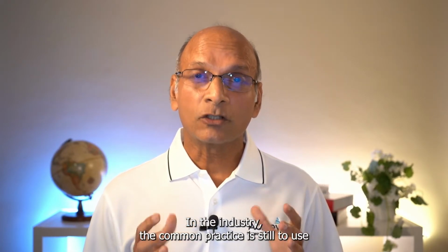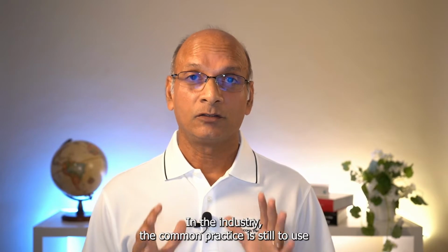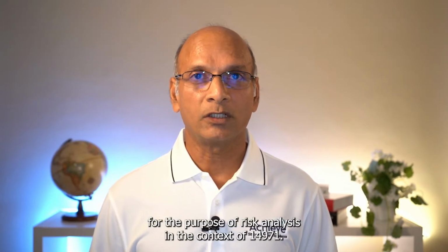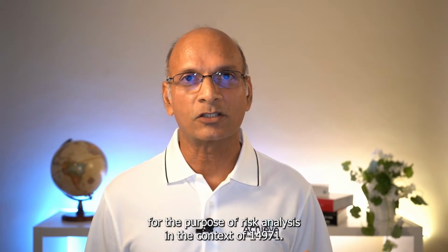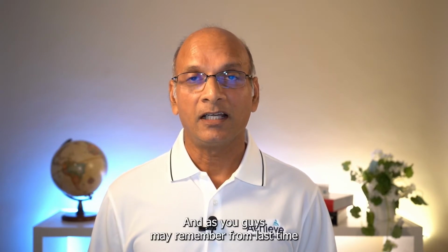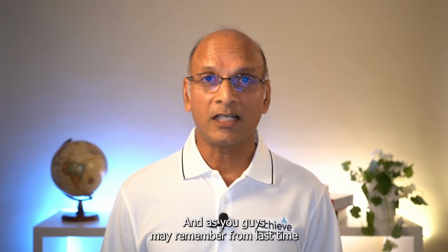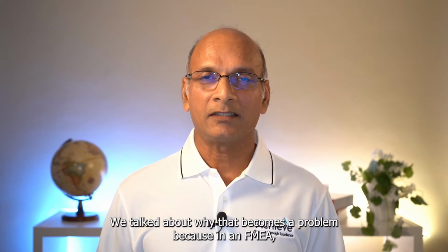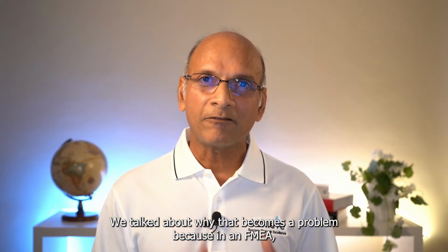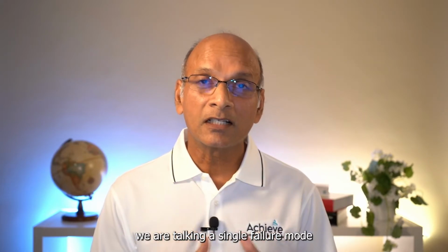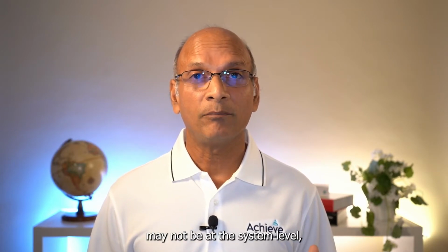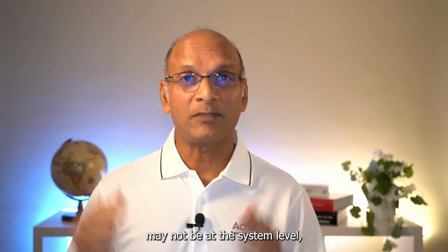In the industry, the common practice is still to use FMEAs, failure mode effect analysis, for the purpose of risk analysis in the context of 14971. As you may remember from last time, and if you did not attend, there's a recording available you can watch, we talked about why that becomes a problem, because in an FMEA, we are talking about a single failure mode. And the effect of that failure mode may not be at the system level.